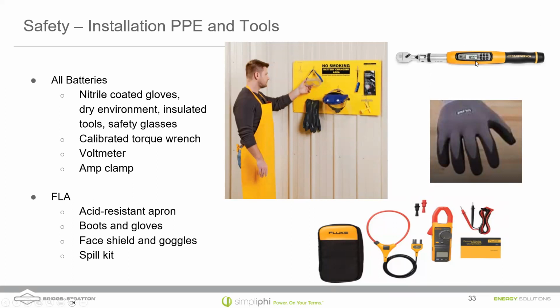And of course, with our batteries, you have a breaker there, so always make sure to switch that breaker off. One of the reasons we keep that breaker is for safety, you can isolate components of the system. So pay attention, and if possible, use an insulated torque wrench to tighten down the battery lugs.